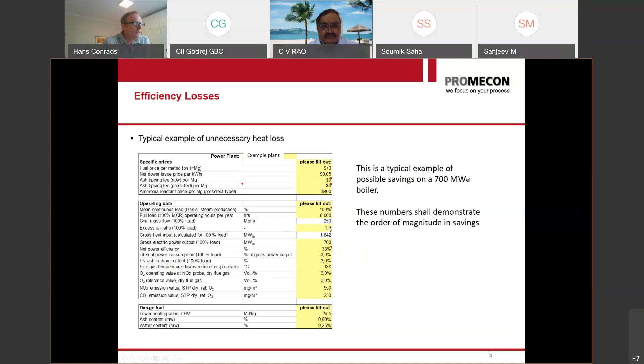If you reduce the excess air by 4%, if you reduce your unburned carbon content in your fly ash and your NOx, you would easily come up to a fuel saving of $1 million per year. Now, this is for international coal. If you have Indian coal with a much higher ash content, then your unburned carbon reduction will be much lower. Only a few tenths of a percent will give you a similar saving in coal. Why am I saying that? The potential of savings just by optimizing primary settings on your boiler is gigantic, and it's efficiency, NOx, and load flexibility.